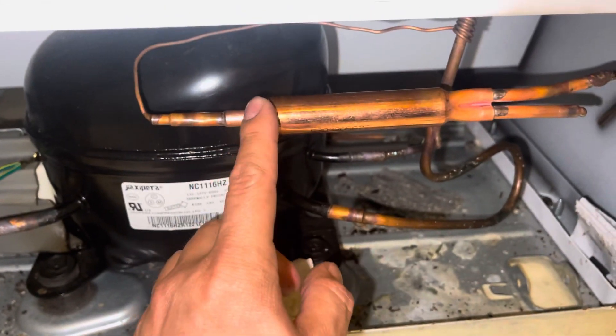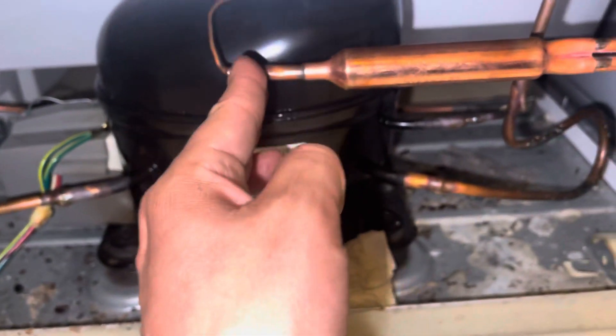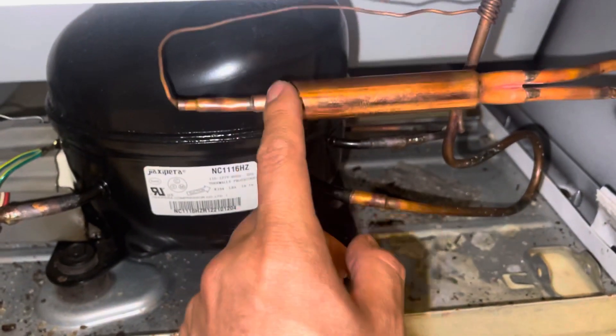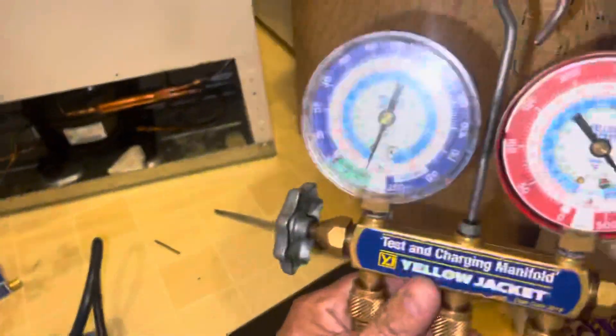This is the new filter that we installed already, and we ended up putting a Schrader valve. Long story short, this unit was having a restriction on the filter dryer, and at that point we had to replace it completely. We already ran a vacuum — the vacuum pump is done and everything is now under vacuum.